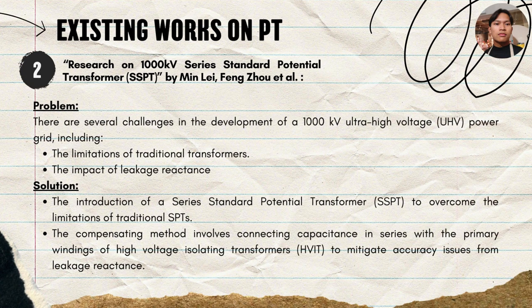For the second research paper, it discusses the challenges in development of 1,000 kilovolt ultra-high voltage power grids, including the limitations of traditional transformers and the impact of leakage reactance. The solution introduced is a series standard potential transformer to overcome the limitations of traditional SPT, and also a compensating method involving connecting capacitance in series with the primary windings of the HVIT to mitigate accuracy issues from leakage reactance.